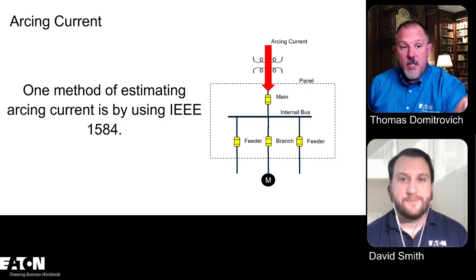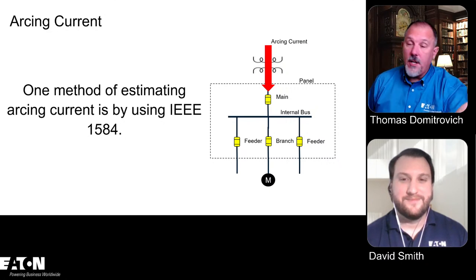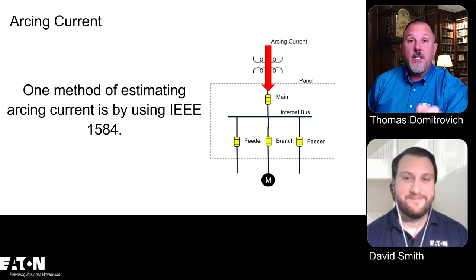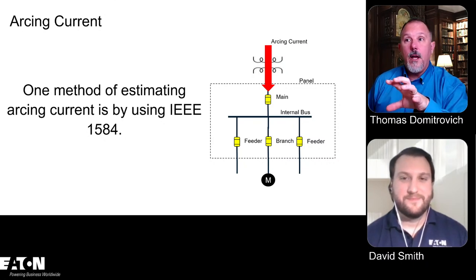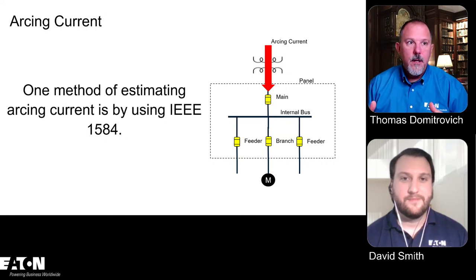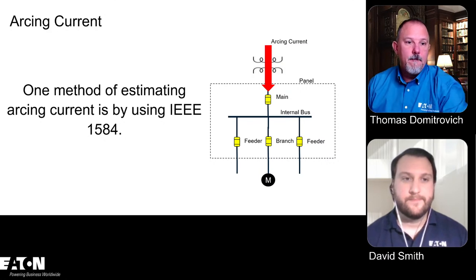Now, when it comes to the arcing current, I agree with you, Daryl. The arcing currents are probably going to be different based upon real equipment. But I would say available short circuit currents are going to be different if you actually had a fault in a power distribution system. It's not going to be exactly what you calculated because we don't account for a lot of different impedances or whatnot. But we do the best we can with the equations that we have to meet the code requirements and to come up with designs. That's the best I can do.